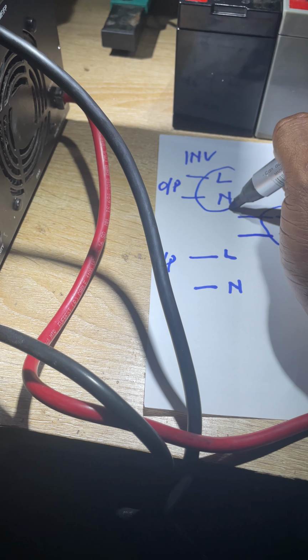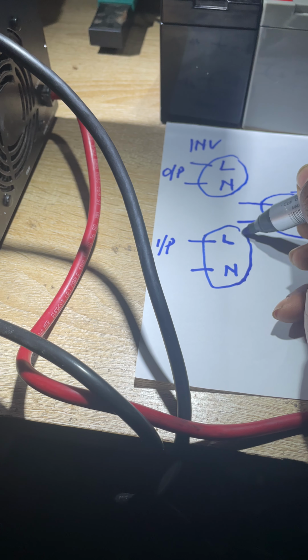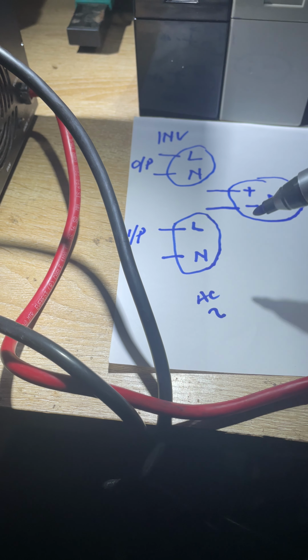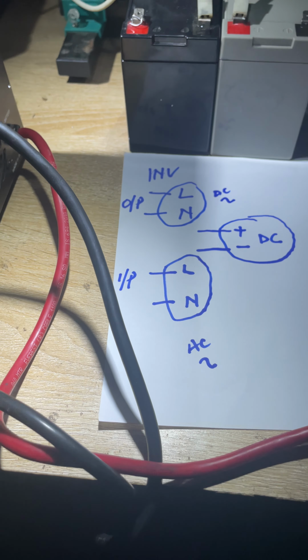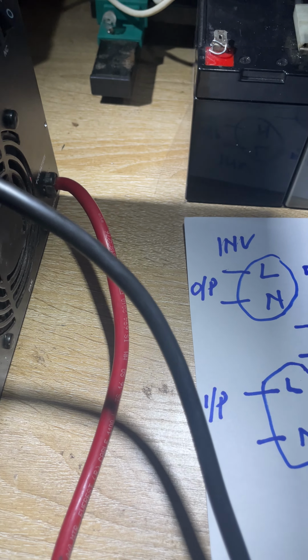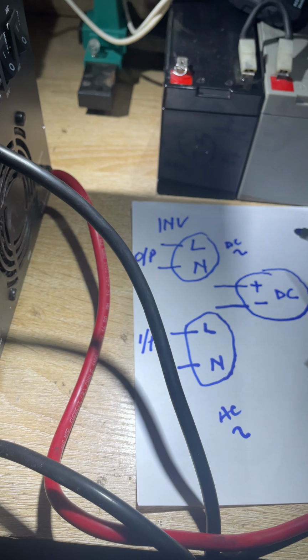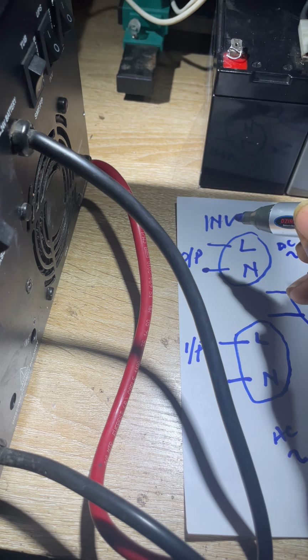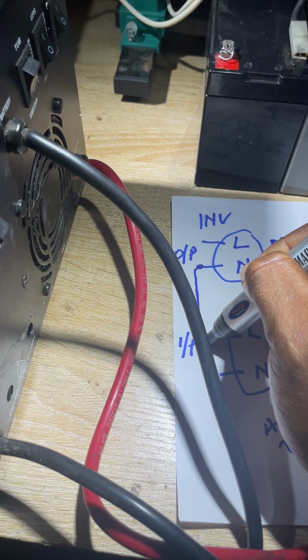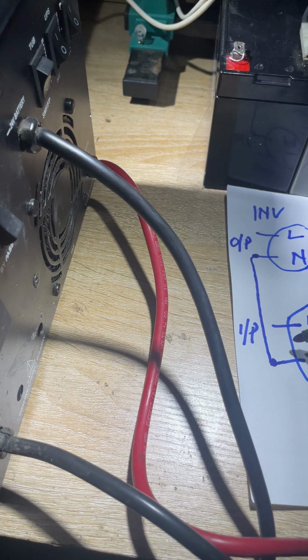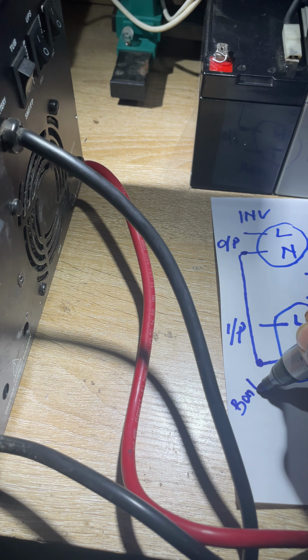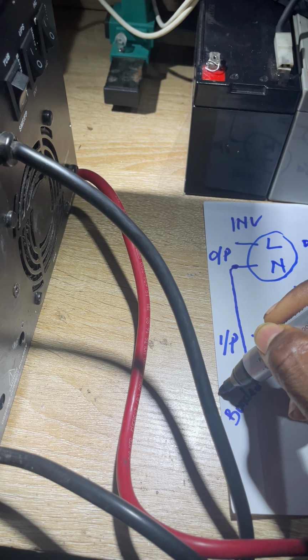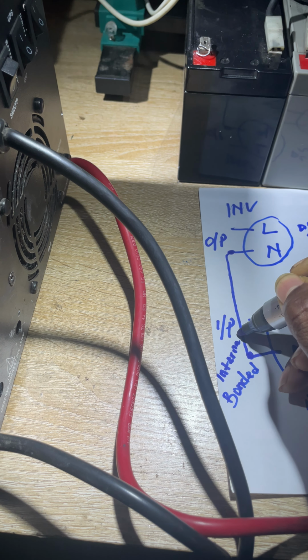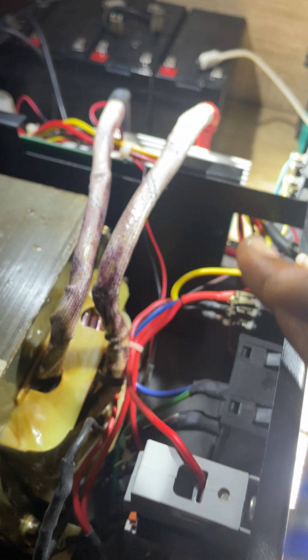The other two sections are AC. Now, inside the system, after the topology, after the connection of the MOSFET board and all that, through the relay, the ATS section and all that, the neutral part of the outputs and the neutral of the inputs is bonded, which I refer to as internal bonding. Inside the system, it's bonded.